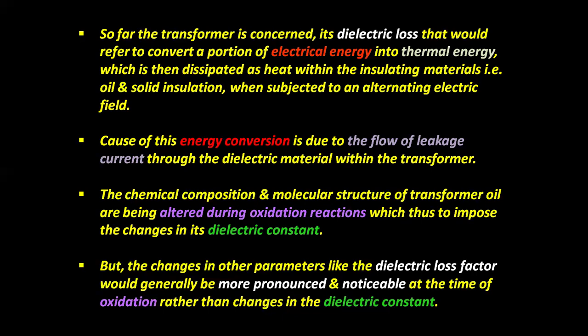The chemical composition and molecular structure of transformer oil are altered during oxidation reactions, which imposes changes in its dielectric constant. But changes in other parameters like the dielectric loss factor are generally more pronounced and noticeable during oxidation than changes in the dielectric constant.